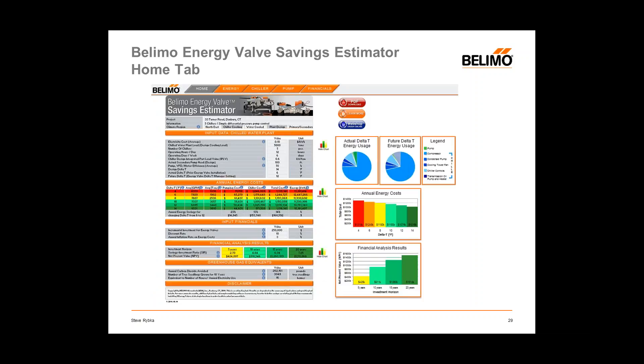On the home tab of the Belimo Energy Valve Savings Estimator, note the show chart tabs to the right of the sheet. Selecting these tabs will reveal graphical charts for energy use based on current and future delta T, annual energy costs pertaining to plant delta T, and a final financial analysis associated with making delta T improvements. You'll also see I buttons — small round blue buttons throughout the Excel sheet — on the home sheet, energy sheet, chiller sheet, and pump sheet.